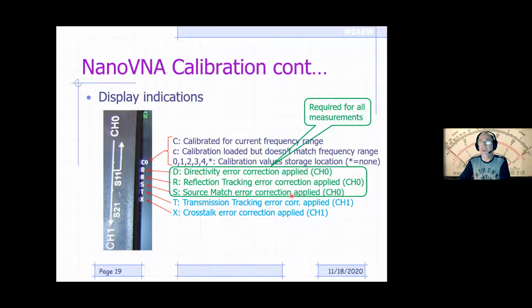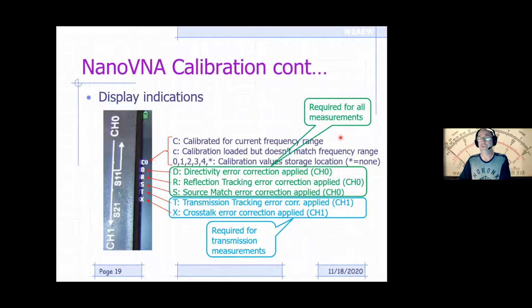This first set, the D, R, and S, are essentially the measurements that are made by applying the calibration standards to channel 0. That's required essentially for all your measurements. These latter two are only needed really when you're making through measurements, using both ports. If you're only going to be making single port measurements, you don't really have to do that second half of the calibration. So this is the actual process of how you do it. And I just went through this just to kind of show you how you walk through menus as well.